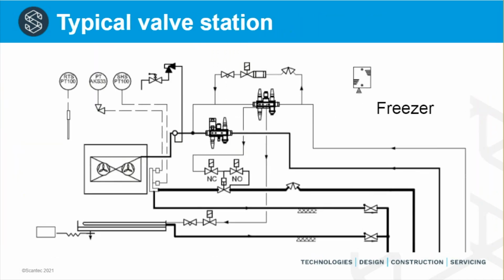Here you see a picture of the valve station used for the freezers. It's no real surprises here. You can see it is all quite conventional. The main differences are these. There is an oil drain from the distributor, the liquid distributor, the inlet evaporator. There's two hot gas solenoid valves, one for the condensate tray and one for the coil.